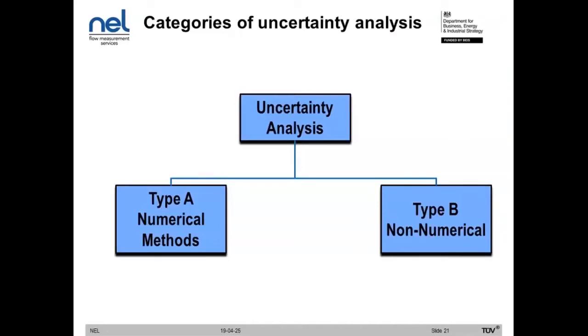Type A uncertainties are based on statistical analysis of large data sets, so it's the most mathematically robust type of uncertainty analysis, whereas type B comes from less statistically interesting techniques. Type B analysis might be from a calibration certificate, for example. So there has been uncertainty analysis applied, but you're just taking a single value as your answer. Or it may be from manufacturer specification sheets, or from past experience and the advice of a consultant. The point here is that you don't have a large data set to perform a calculation with. You have maybe a single value or a small range of values. The examples we're going to give today are mostly going to be type A numerical uncertainties, but type B are important as well.